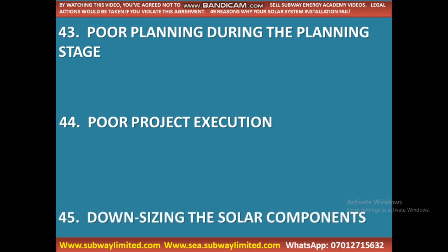Downsizing the solar components - what do I mean by downsizing? If you are having 5,000 watts of loads and you are using a 3 kVA inverter, the system will surely shut down. If you are having 3,000 watts of loads and you are running a 1 kVA system, you will overload the system. That is downsizing.